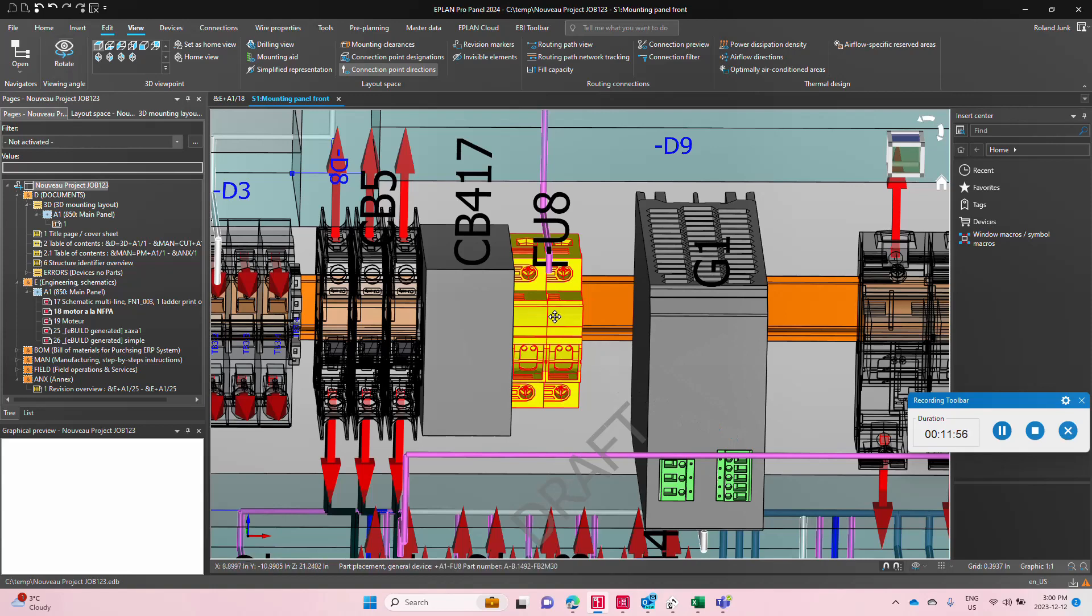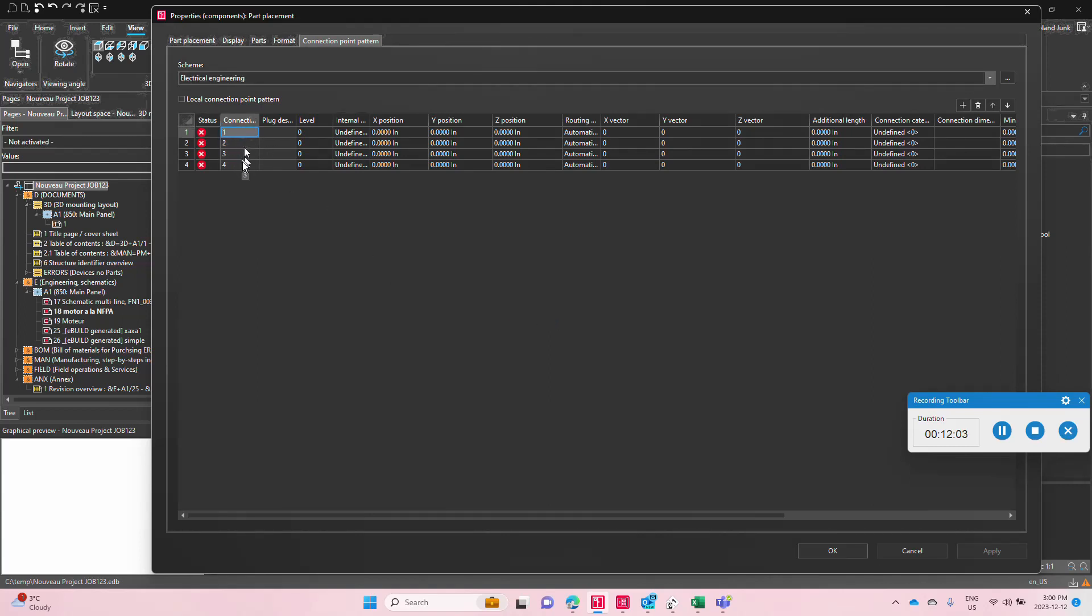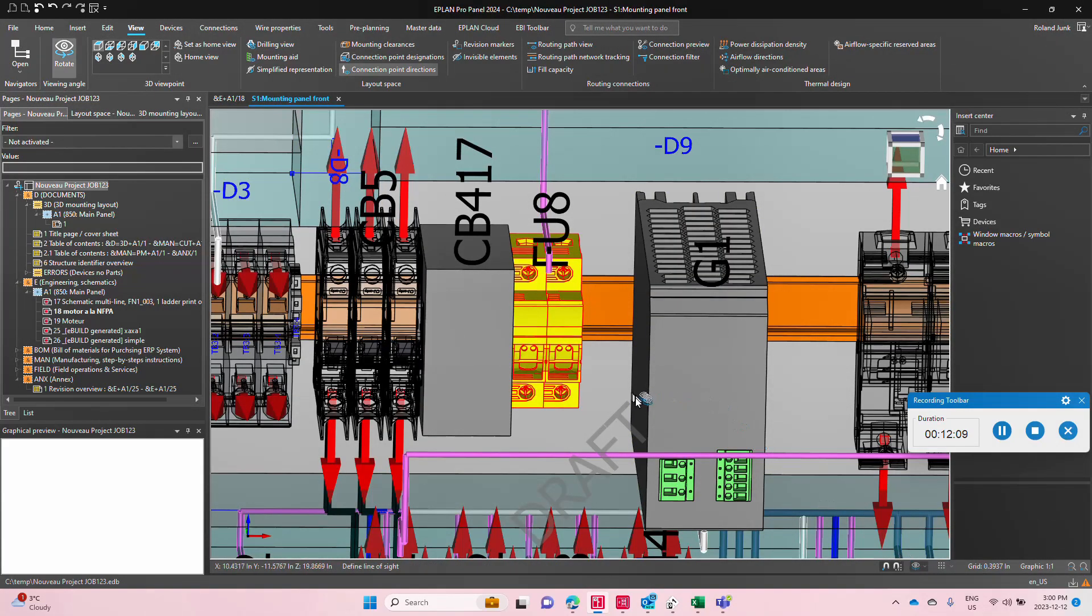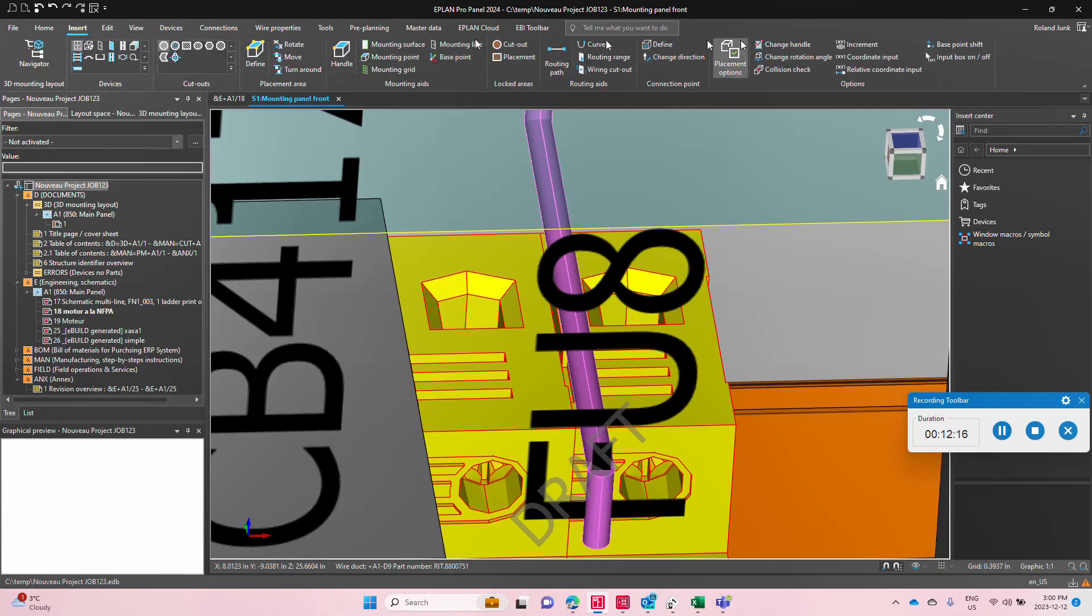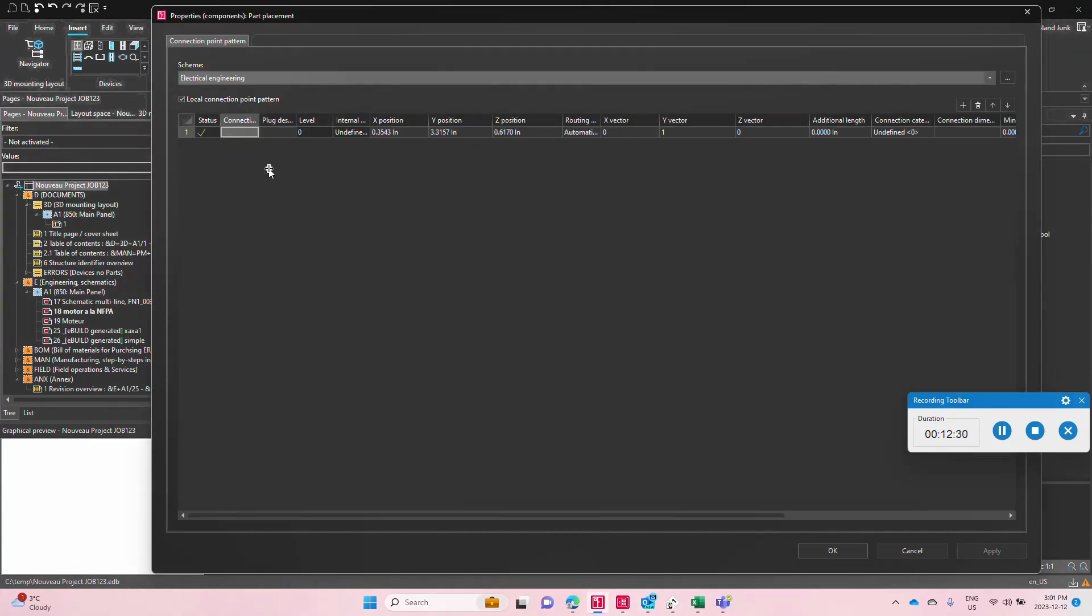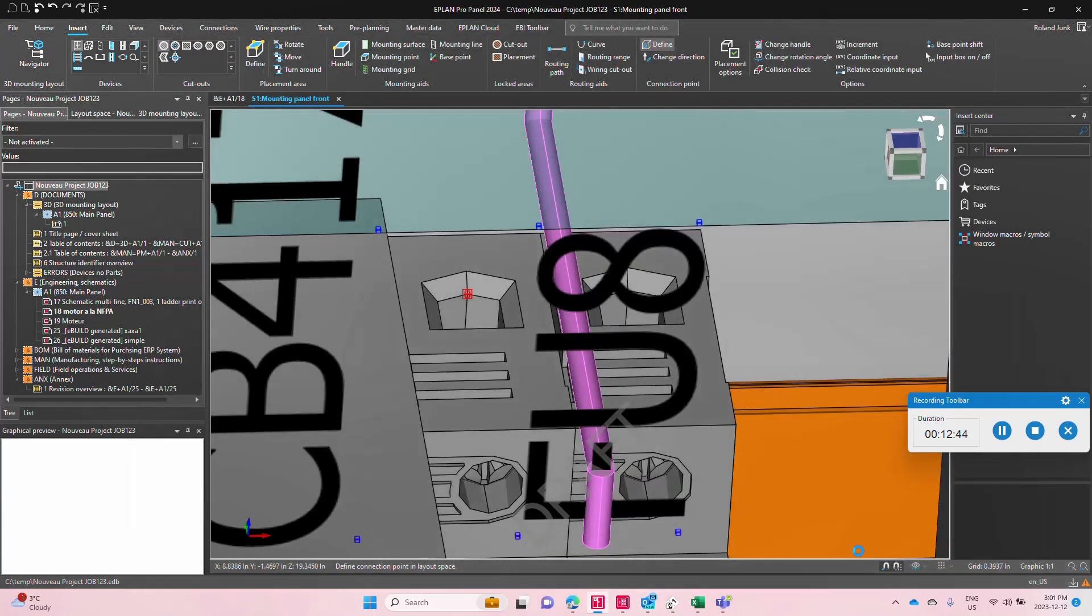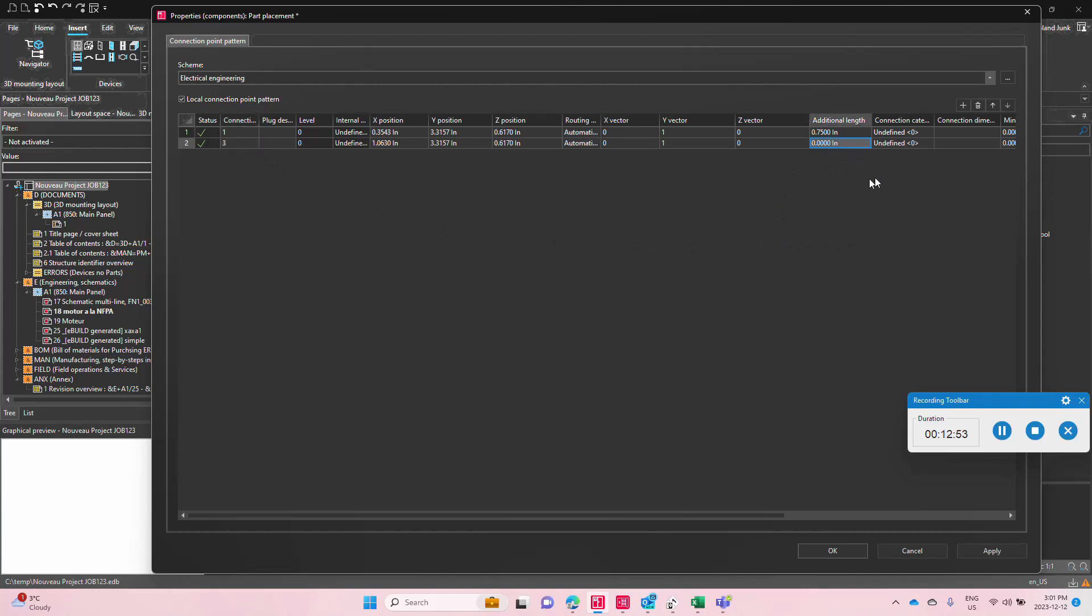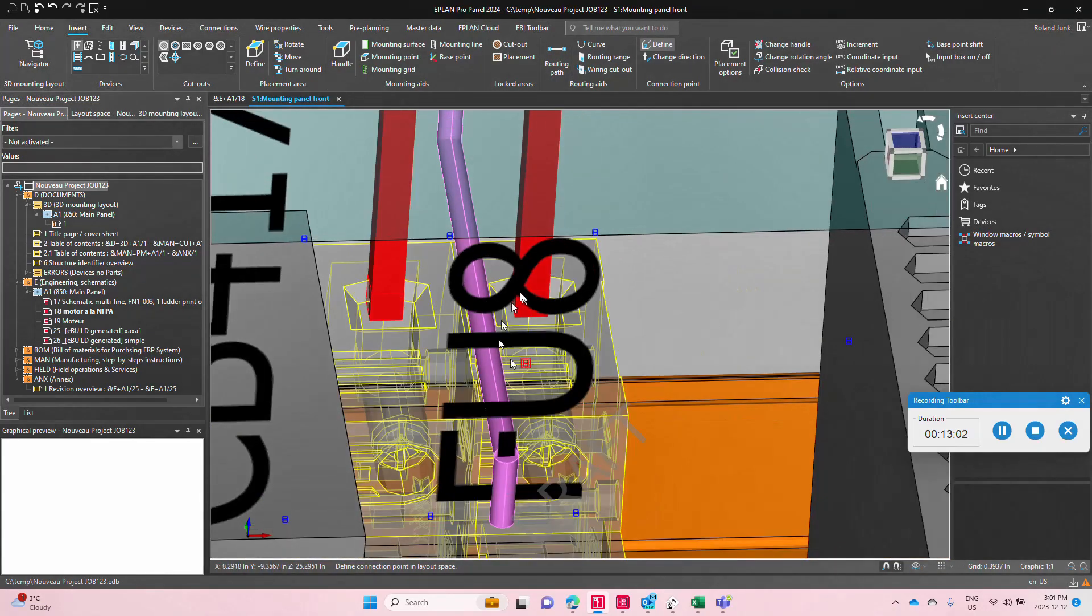All it does, it actually calculates the wire length to the center of the component at the very top. But we actually know that 1 and 3 are actually going to the top. And where are they coming in? Let me just quickly define them. It only takes a few seconds, really. All you have to do is here, insert what we call a connection point definition. So you choose the surface here to actually align the wires going out. And then you can say, let's take the bottom portion here. That would be my connection number one, obviously. Now, of course, because I'm on the far outer corner, I would maybe add here like a 3 quarters of an inch, just to go inside a little bit further in. And there we go, we have the first connection. Now, in the same alignment, I can actually place this one here, which will be connection number three, and then say, add also like a 3 quarters of an inch, actually make sure the wire goes far like 3 quarters inside.